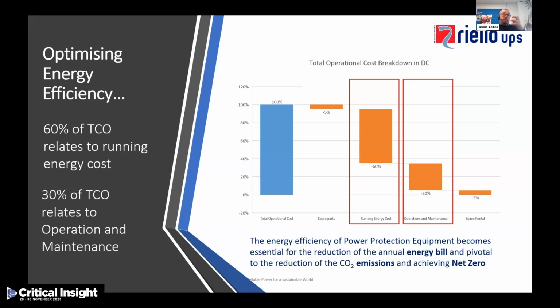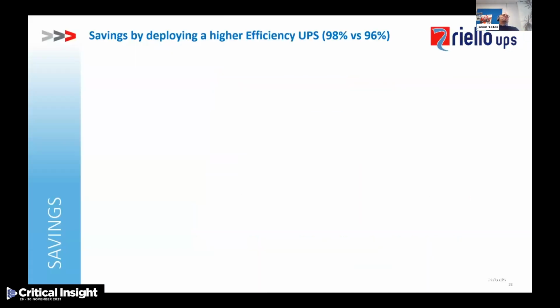And that's why we've pushed it into not just the environmental impact, but we've specifically designed around these two areas. If we look at the savings that can be achieved by deploying a high efficiency UPS, this is an efficient UPS system, a new system, where you've got a 98% efficient UPS versus a 96.1%, which is still a very high performing UPS system.